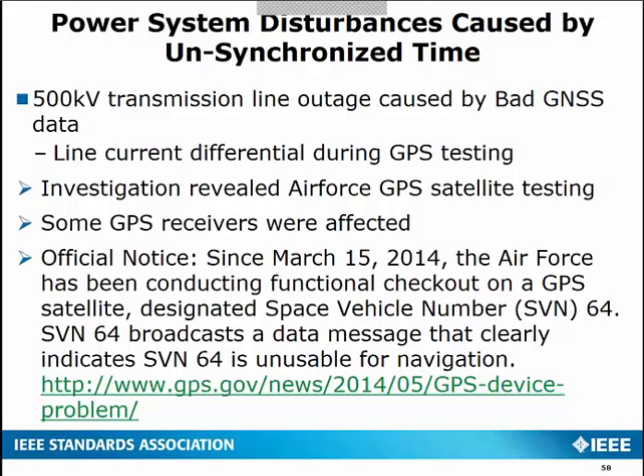Now, going on to an example of when an unsynchronized timing causes an event. Back in March of 2014, the Air Force was conducting functional checks of space vehicle number 64. Well, this led to, we had a couple line differential relays, if you remember, line differential relays synchronize the current signals at both ends of the line using the GPS. Well, one of the relay's GPS receivers incorrectly logged onto this satellite that was under test mode.